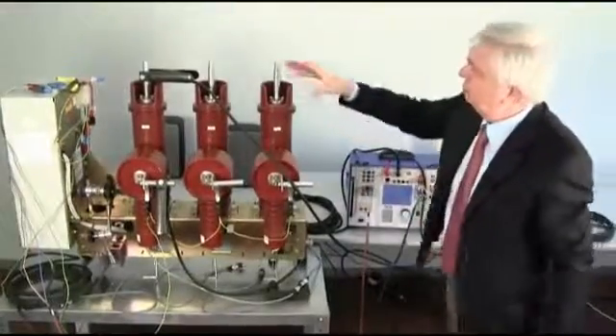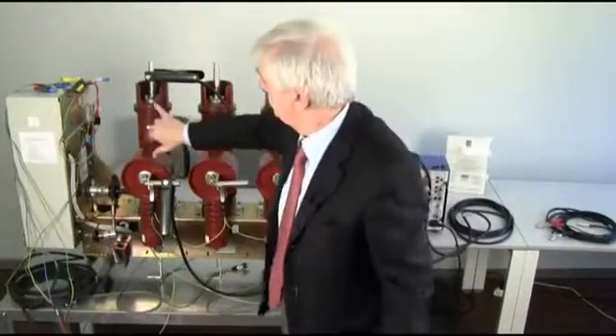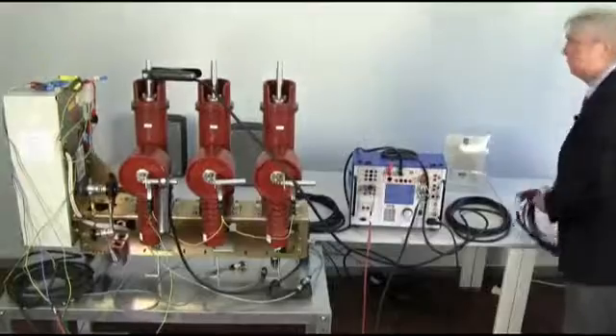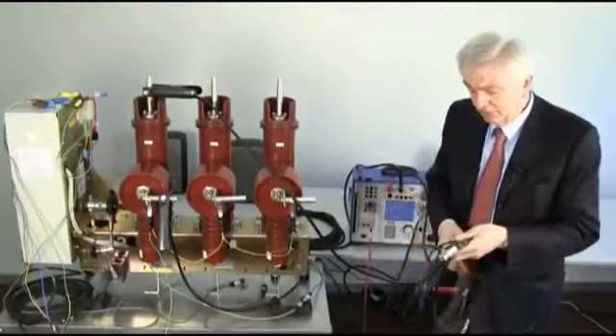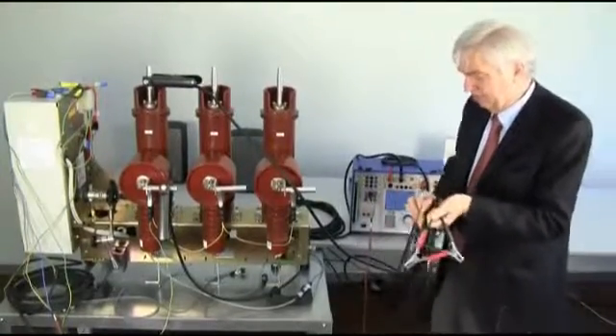Now, what do we do? It is very simple. We inject a very high current into the closed contact and we measure the voltage drop across it. How do we measure it? With this other cable, this is a shielded cable.